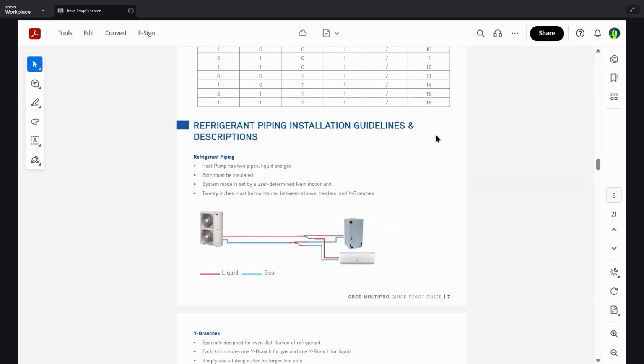Refrigerant piping installation guidelines and descriptions. This heat pump has two pipes, liquid and a gas. Both must be insulated. System mode is set by the user to determine main indoor unit, or is selected randomly by the system if you do automatic addressing. A lot of these same things apply, so we know that 20 inches must be maintained between elbows, headers, and Y branches. And here's an explanation or an example on how those Y branches are actually laid out.